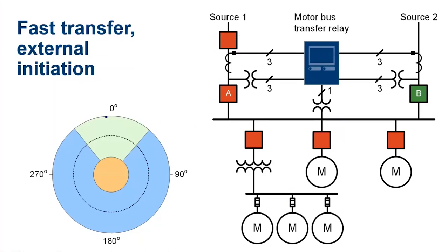For example, if we have 2 completely independent sources, say one is coming from our own generation and the other is coming from an independent system such as the utility, then the phase angle between these 2 systems might be very, very large. It could be 180 degrees apart because the systems are separate. So in those systems, we wouldn't allow for a fast transfer. The relay will do a live check of the phase before attempting a live fast transfer. But in any case, you would only want to allow these kinds of transfers when, in principle, you have the 2 systems, the 2 feeders, with a close enough phase.